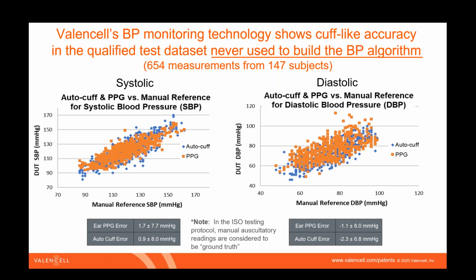Another thing is if you look at the bottom of each of these, you can see where I've summarized the statistics. Now, to pass, the ISO protocol looks for a mean error no greater than 5 millimeters of mercury, and a standard deviation error no greater than 8 millimeters of mercury. And we were able to achieve that on this qualified test data set for both the systolic and the diastolic. You'll note that on the systolic side, it looks like we did a little bit better than the autocuff. That is not true. This is within the margin of error. 7.7 millimeters of mercury versus 8 in this particular case, that small 0.3 is just in the noise. We can't say we're better than a cuff.